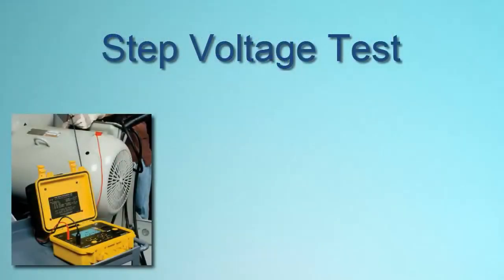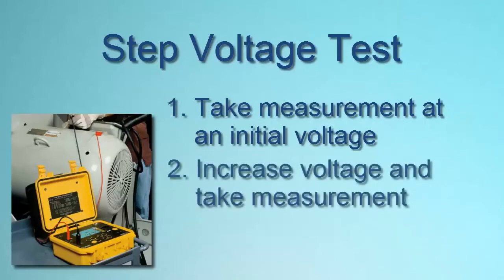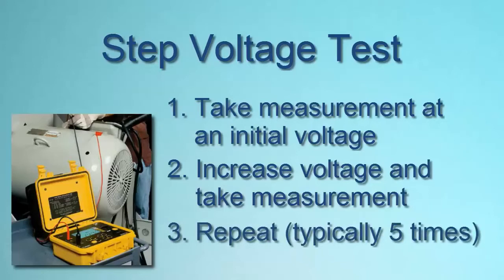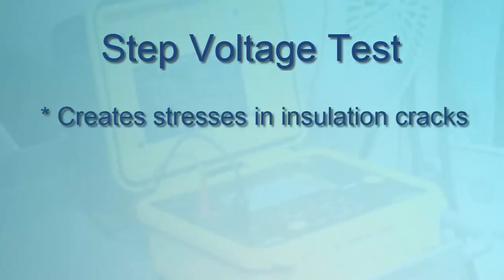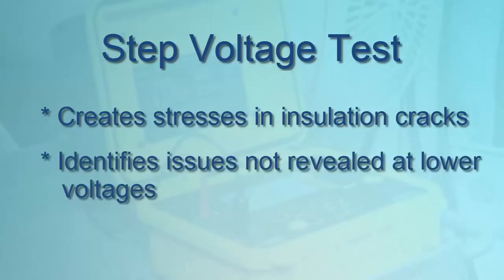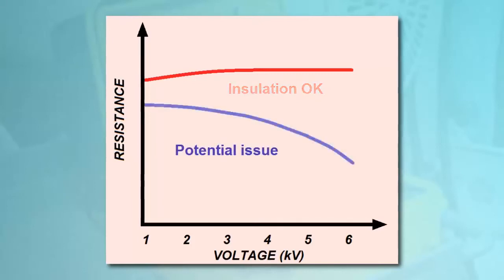A third method is the step voltage test. This involves testing at two or more test voltages and comparing the results. The test begins at an initial test voltage. At a specified interval, typically one minute, a measurement is recorded, after which the test voltage is increased — usually to five times the initial voltage. This process may be repeated through several steps, with measurements taken after one minute and the test voltage increased at a 5-to-1 ratio over the previous voltage. A common practice is to test at five voltage steps. The step voltage test is designed to create electrical stresses on internal insulation cracks, identifying potential problems that may not be revealed by testing at lower voltages. Insulation that is thoroughly dry, clean, and in good physical condition should provide roughly the same resistance measurement across the voltage range. If you observe a significant decrease in resistance at higher voltages, your insulation may be contaminated or deteriorating.